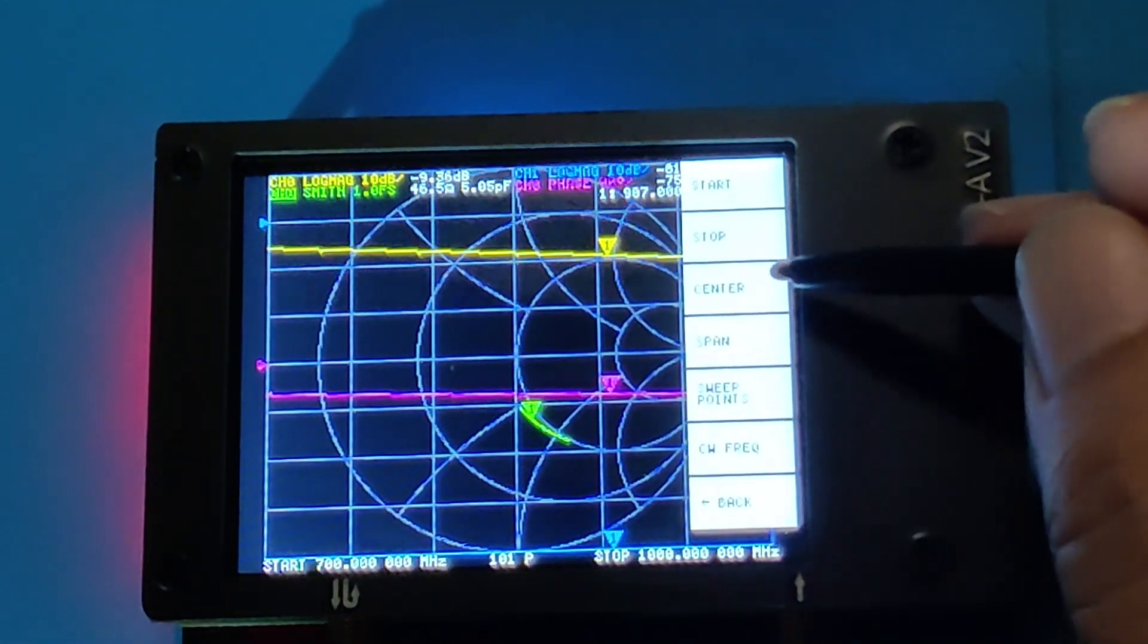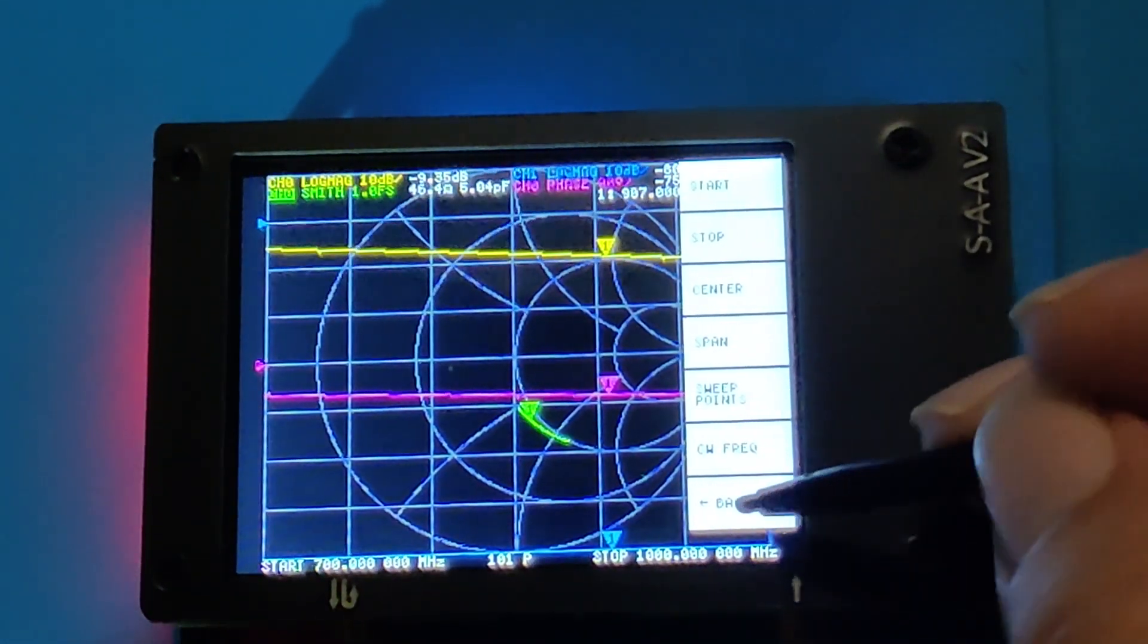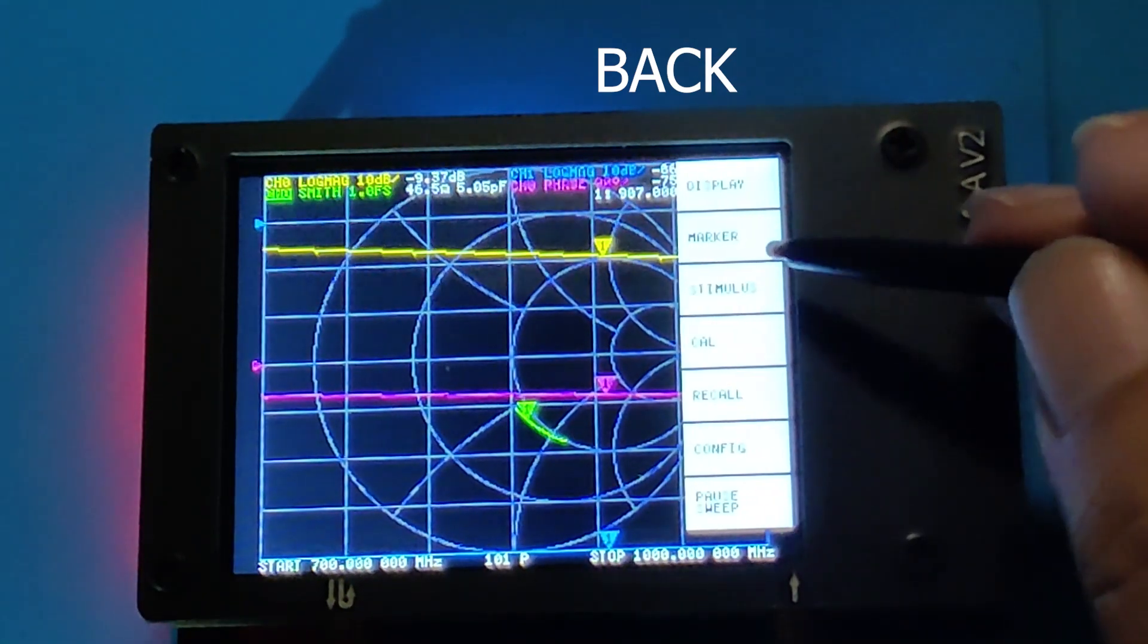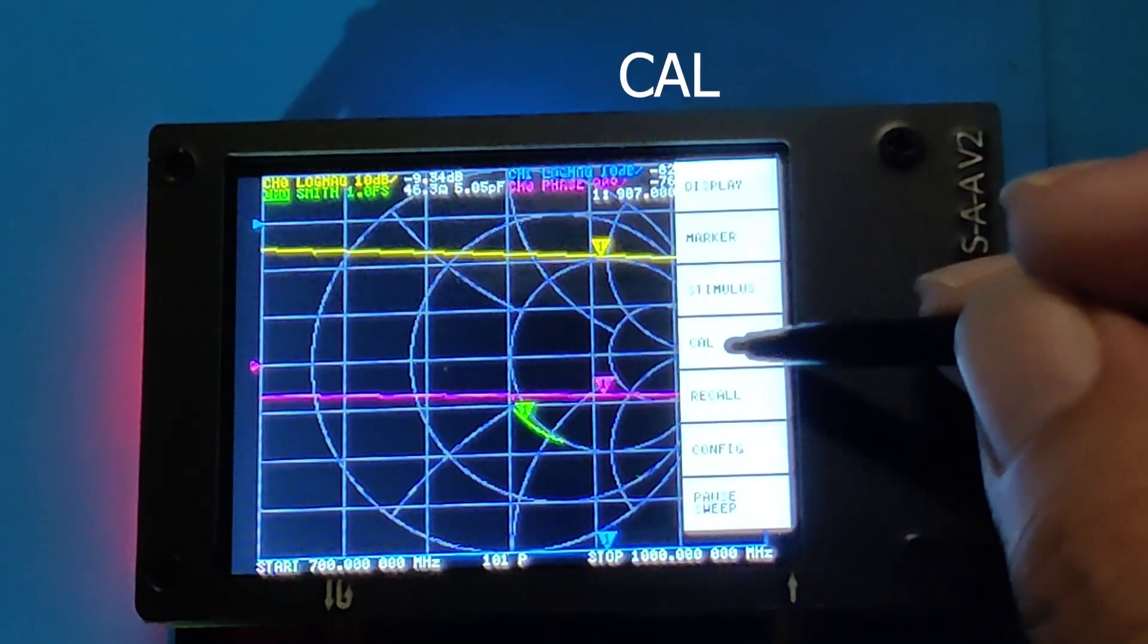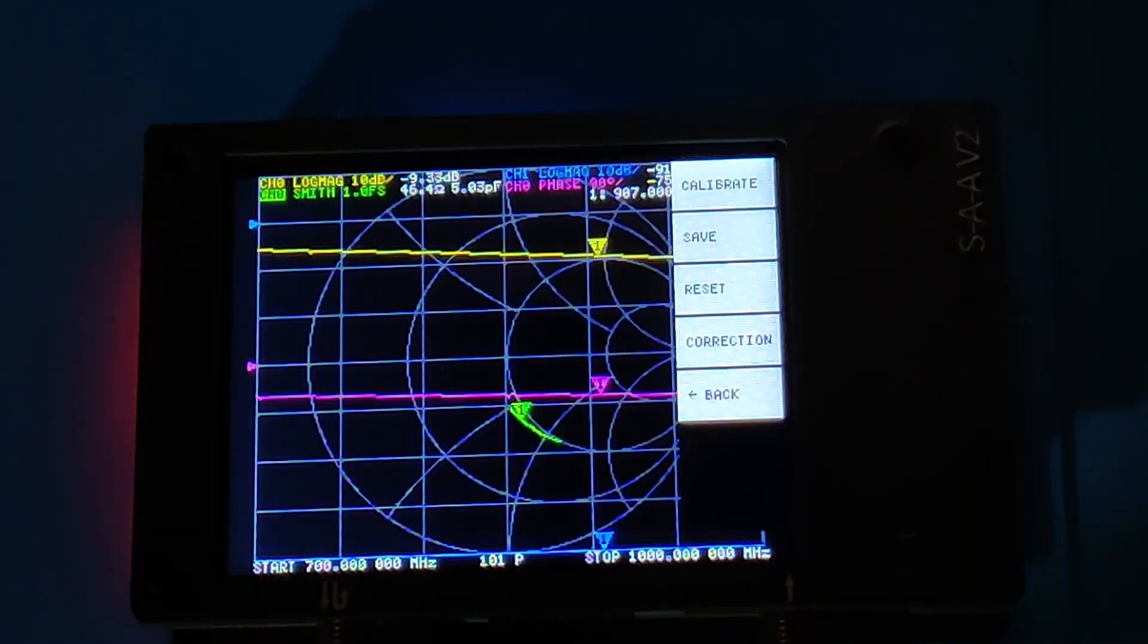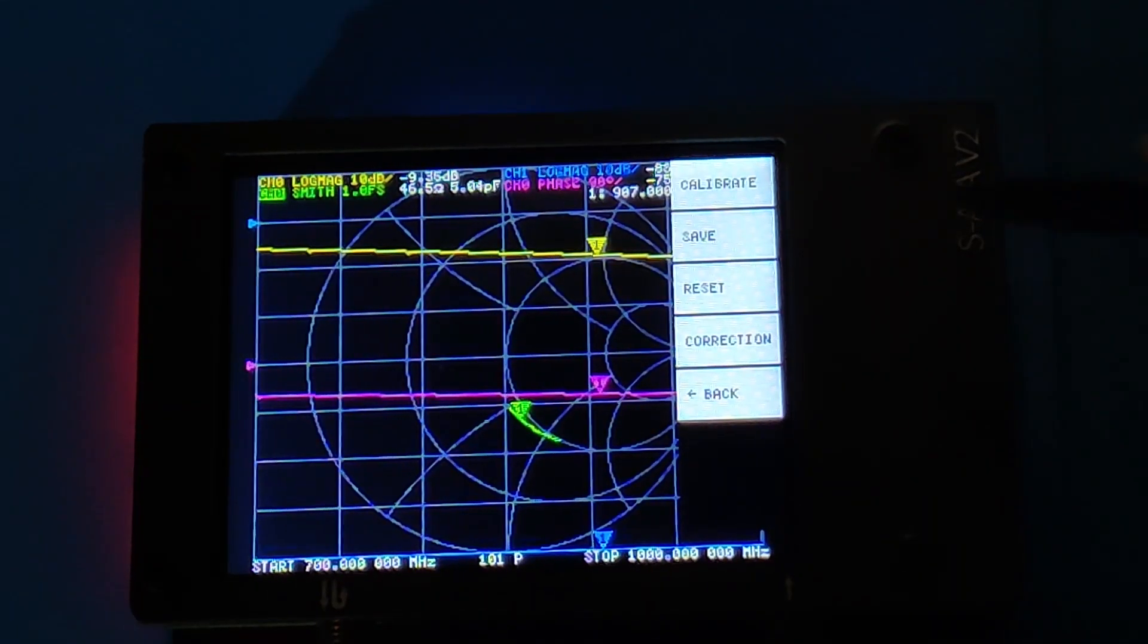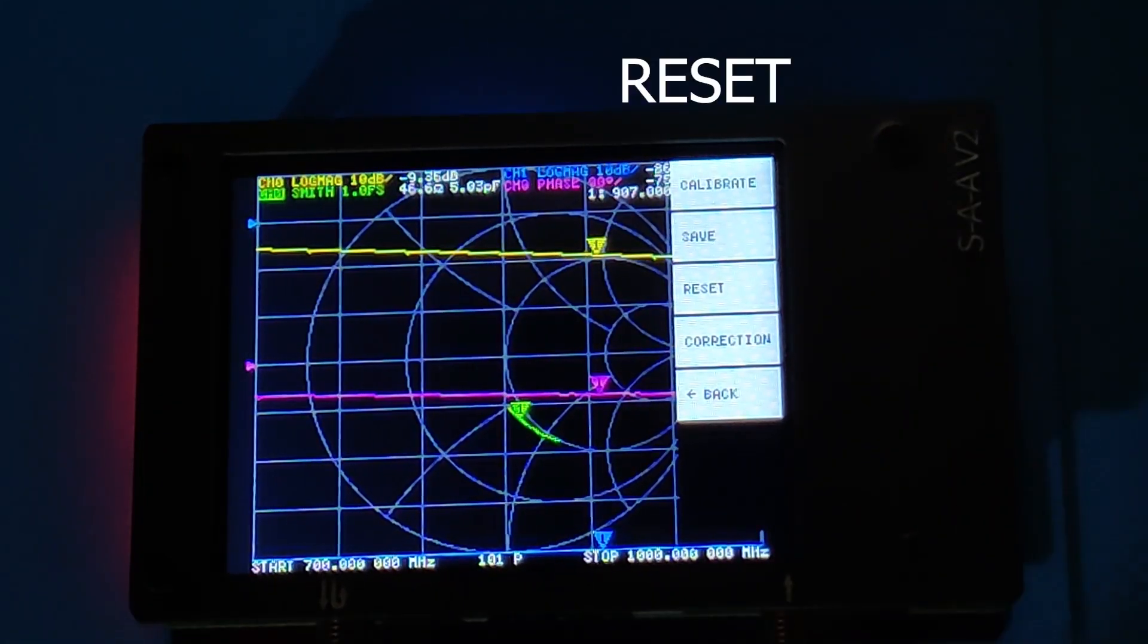After setting the stimulus, we go one step back to the previous menu and click on CAL or calibration. To clear any calibration present in the RAM, we click on the reset menu item.